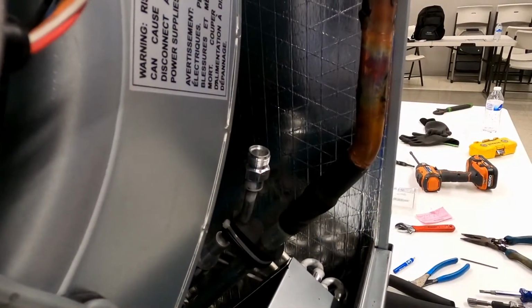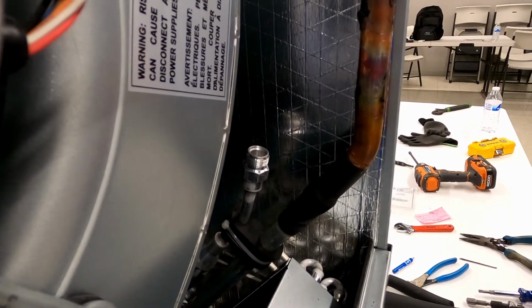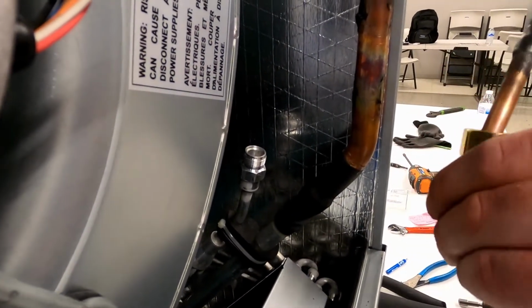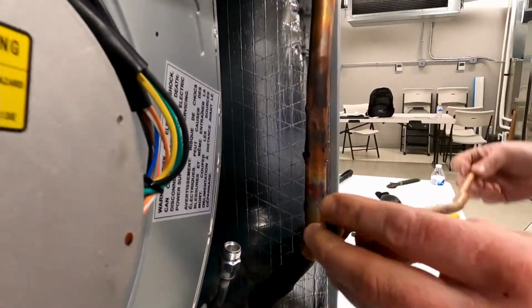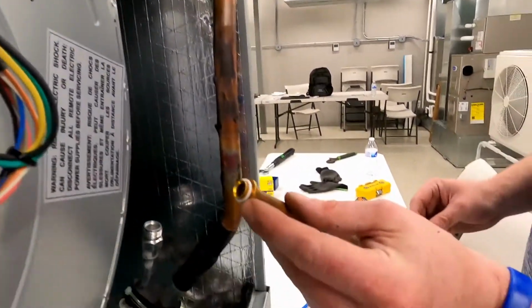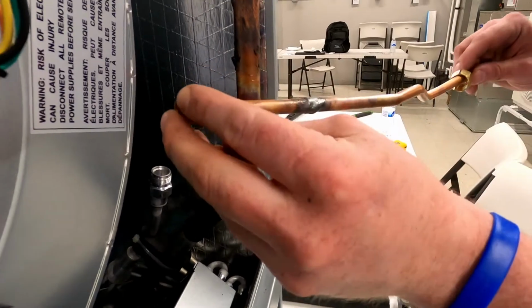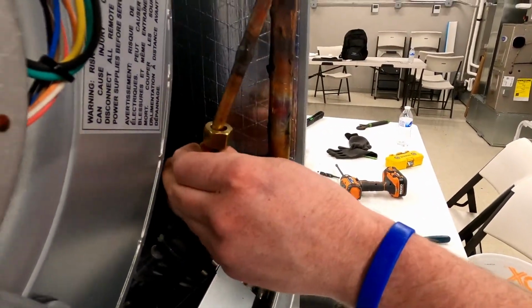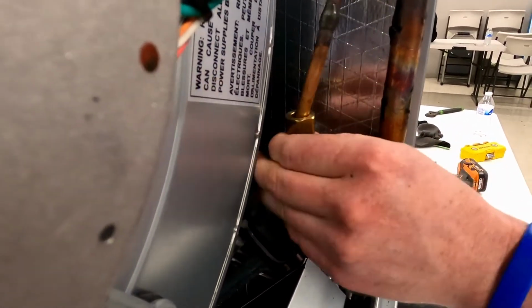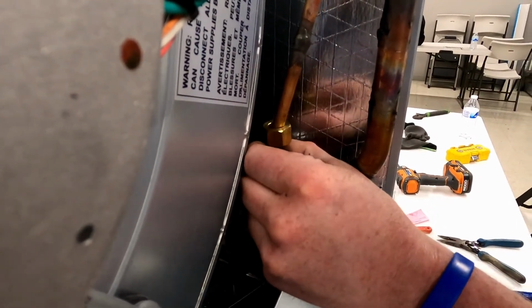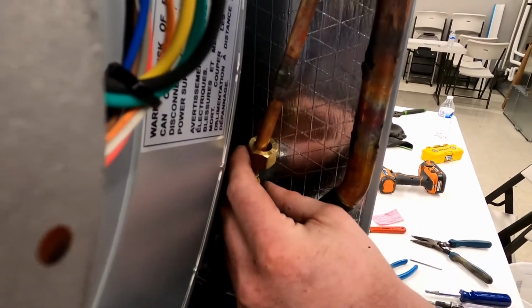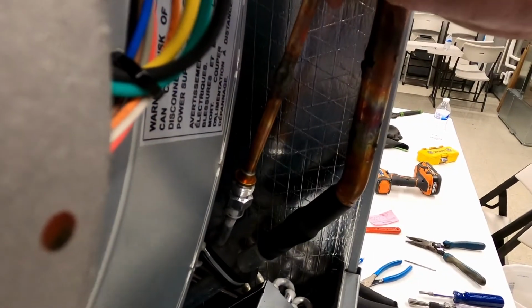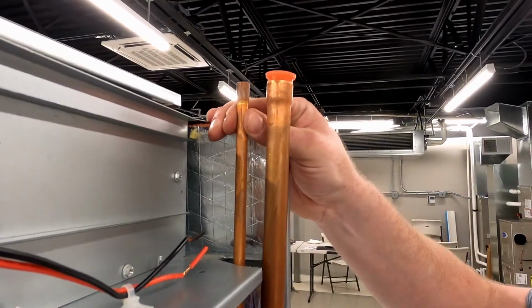All right, so now that we finished brazing our adapter fitting to the original piece of pipe that we removed from the expansion valve, now we're going to reinstall it in the unit. You want to make sure that you get your Teflon ring on there because that's what actually creates the seal when it's connected to the distributor nozzle. And you want to push it in there, and you want to make sure that it's flush all the way around and everything lines up. And now you can check your fit where it's going to exit the unit. Make sure everything's lined up.